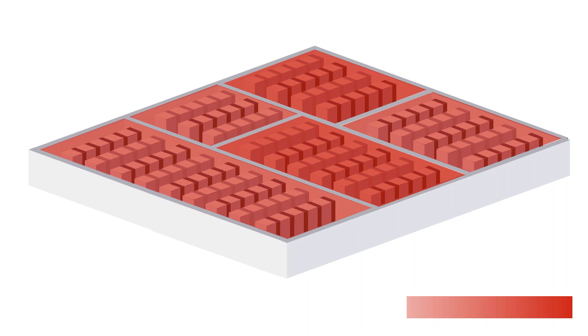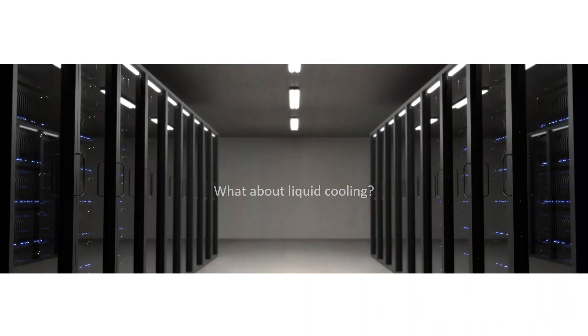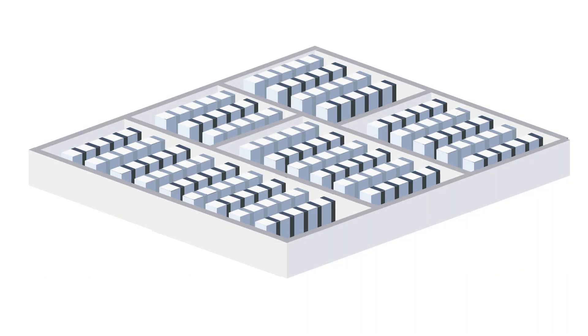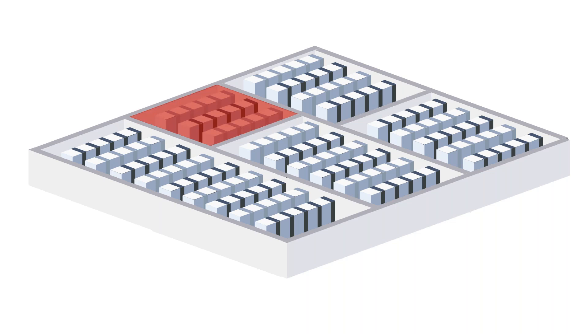All of these things change the loads in all of our spaces. If I close down two floors of a building, the other remaining floors are affected by the change in the hydronic system. Pressure independent valves make all of this go away - they hydronically isolate whatever they're controlling the water flow to. If we exchange that to our heat exchange equipment inside of a data center, we have some real advantage. What about liquid cooling? What if our data center space is all completely balanced out and then one guy comes in and says, I'm going to use rear door heat exchangers and I'm going to need a lot more water or cooling capacity?